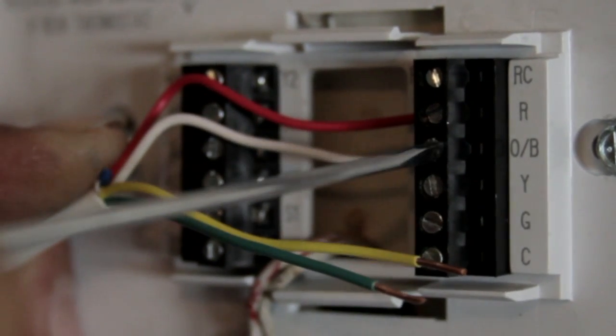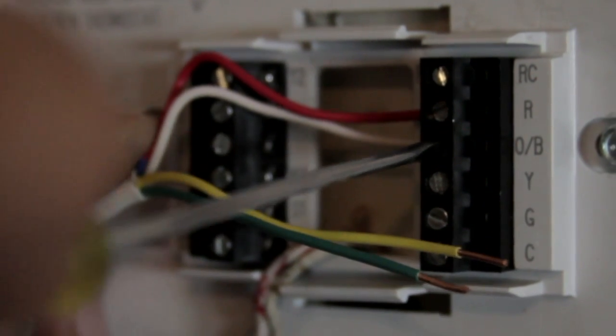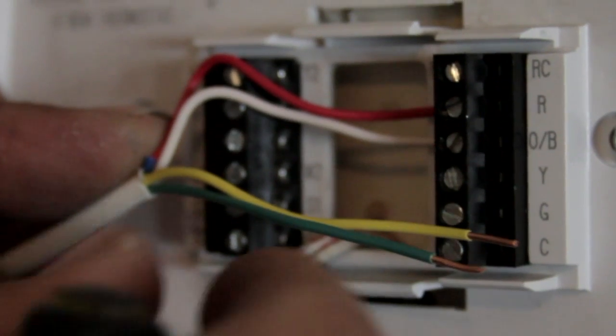One of the things that you want to make sure of when you're actually wiring in a thermostat is to make sure you turn the switch off on the side of the furnace, or you can actually short the control board out or the transformer. W represents heating on this type of thermostat.